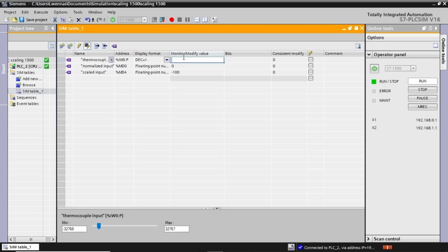We now load the plus 13,824 value, which is the max half. By reason we get 50 in the scaled value. Hope you got the scaling concept well, which is the result of a basic math operation commonly known as the rule of three.